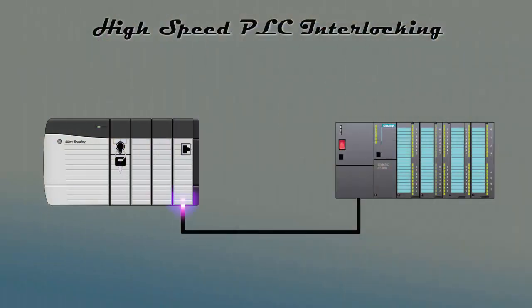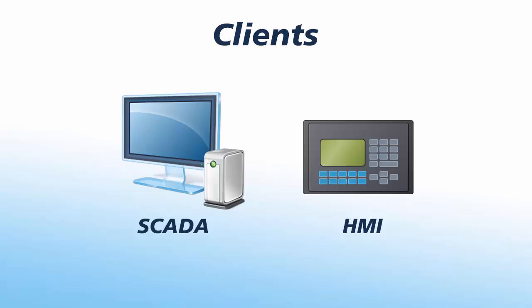I/O messages are designed to run at regular time intervals, meaning the communication speeds are consistent, whereas regular data messaging speeds are dependent on the availability of unused processing power. SCADA hosts, or HMI terminals, on the other hand, are almost always configured as a client.